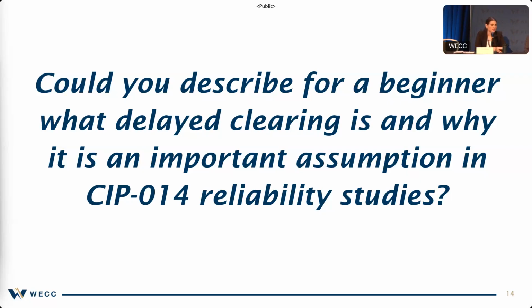That's kind of how I think about delayed clearing. You have localized protection systems that measure and detect faults within a system, with different zones of protection. The zone 1 protections inside a substation are devices that detect something has happened and start triggering switches or breakers to open and disconnect, isolating that fault so it doesn't propagate down into the system and affect other substations or facilities. Delayed clearing is essential because during an attack on a substation, you may not have that spare tire — those devices may not be functioning, they may have been damaged themselves.